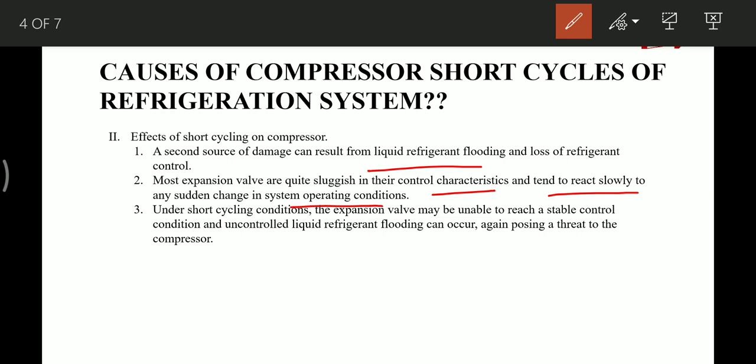Under short cycling conditions, the expansion valve may be unable to reach stable control conditions, and uncontrolled liquid refrigerant floods the evaporator and poses a threat to the compressor. This liquid refrigerant can enter into the compressor and damage the cylinder as this liquid is non-compressible.